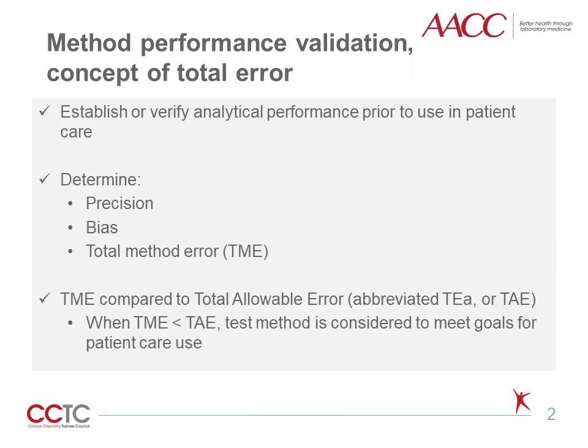Clinical chemists are familiar with the need to establish or verify analytical performance prior to implementing a test for patient care use. These components include precision, bias, and total method error, abbreviated TME. TME is then compared with total allowable error, abbreviated TE sub A or TAE in this presentation.